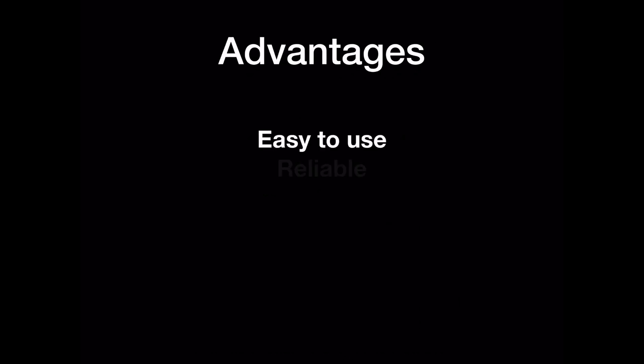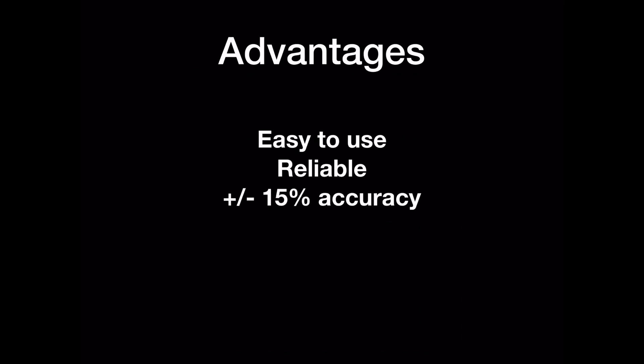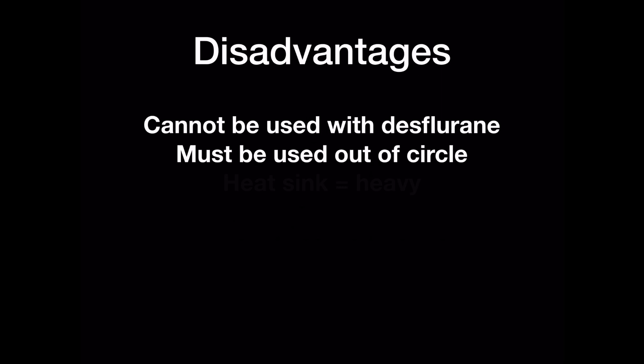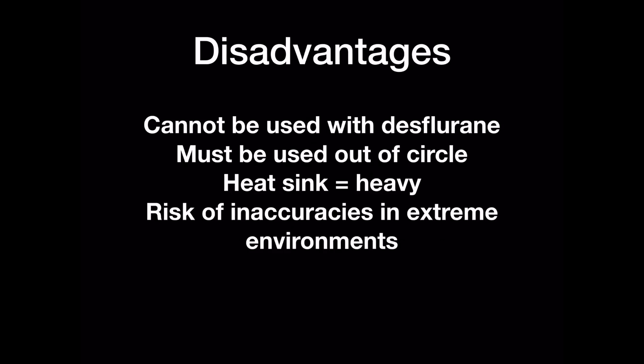Advantages: the plenum vaporizer is easy to use, it is reliable, and when calibrated it is accurate to plus or minus 15% of what is read on the dial. No power source is needed. Disadvantages: it cannot be used with desflurane, it must be used out of circle secondary to its high internal resistance, and the heatsink is heavy, meaning the plenum vaporizer is not easily used in remote settings. If it is used in an extreme environment, anaesthetic may be delivered but there is a risk of inaccuracy.